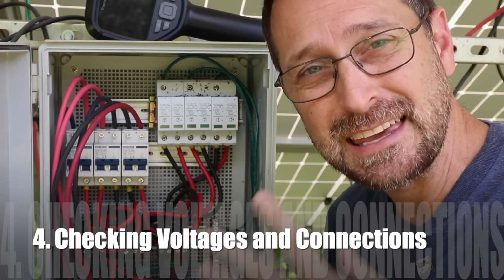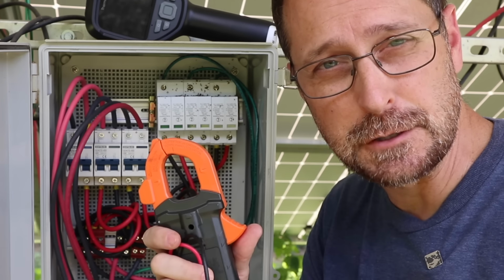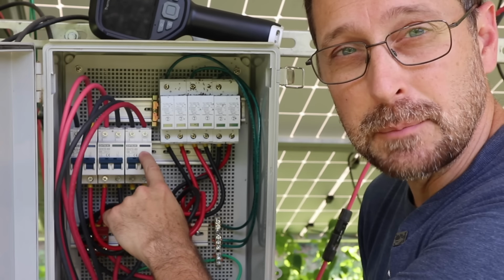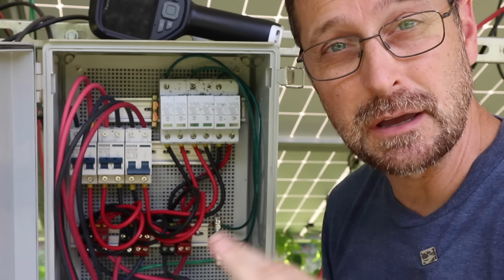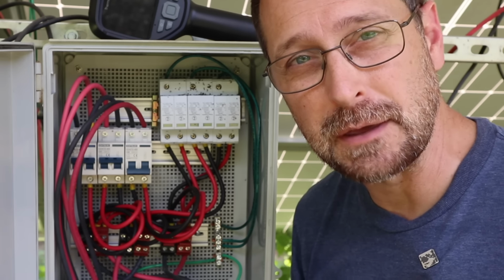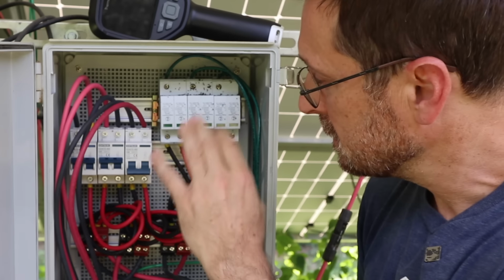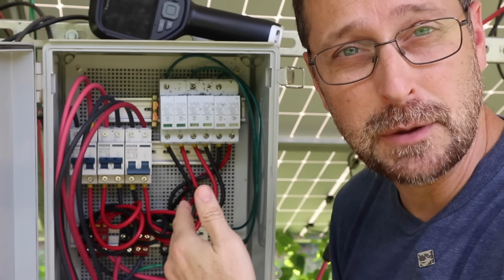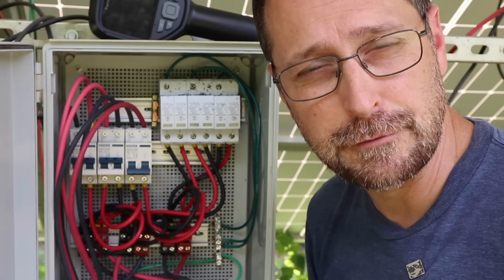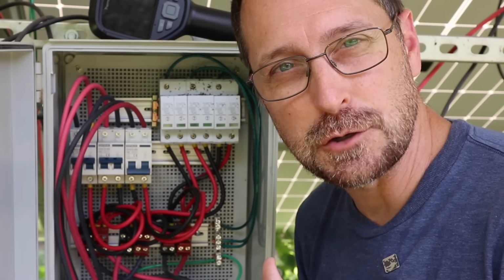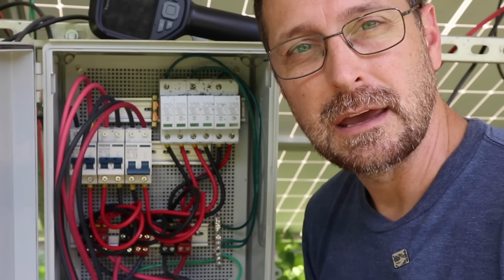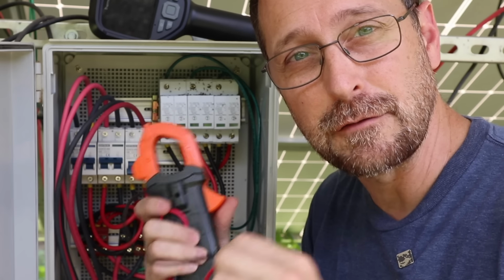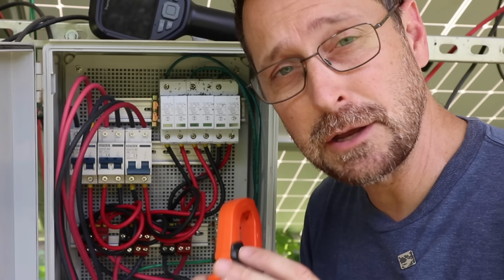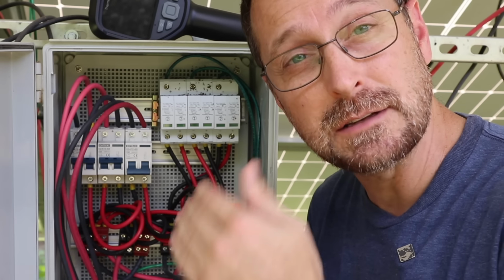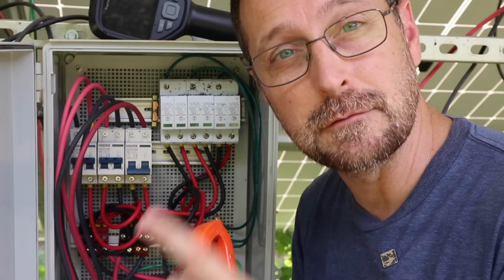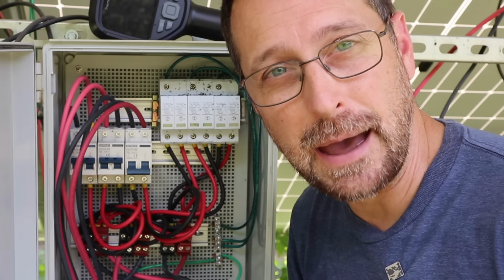One, you can check each panel's voltage individually. What you want to do is isolate the PV string and disconnect that string from your inverter because it is under load right now. Now we've isolated that one, and if you have a different PV disconnect, also turn that off. What we can do now is check each individual panel. Disconnect the wires and go from the positive to the negative on each panel, checking them. You want to make sure the voltage on each panel is the same relative to each other and also relative to the information sticker on the back of the panel.